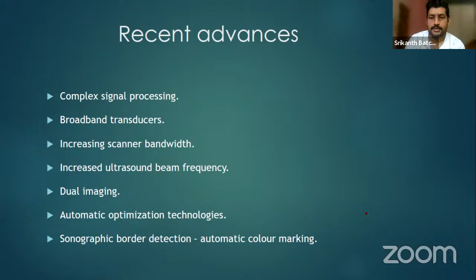which is commonly used in pediatrics. And also the dual imaging technique where you combine modalities. All these days we have been using CT and ultrasound together, and nowadays photoacoustic emission technology and ultrasound technology are used in combination, along with automatic optimization techniques. More and more parameters are added to ultrasound machines, like time gain compensation, so that you can exactly focus on the area which is deep inside. And also, these are actually under research, at least by the time this book was published in 2015: sonographic border detection with automatic color marking. They mark yellow for nerves, brown for muscles, like that. So you can more easily identify what structures are present there.